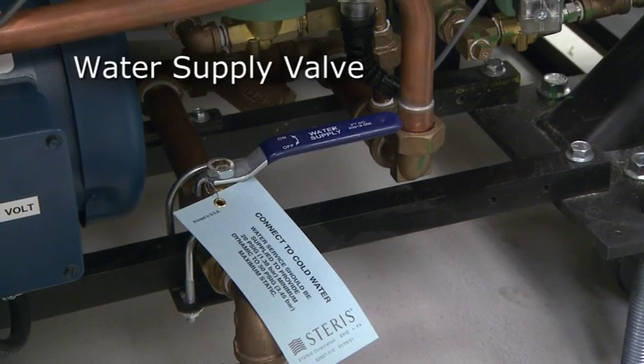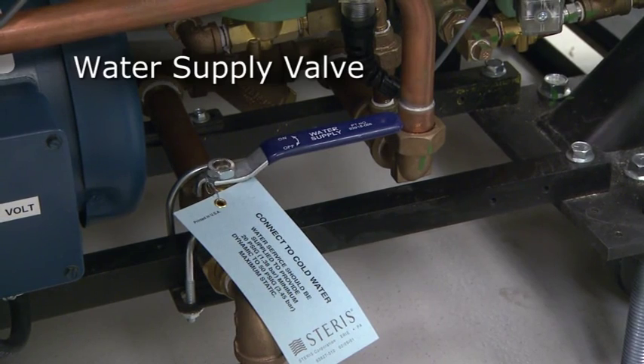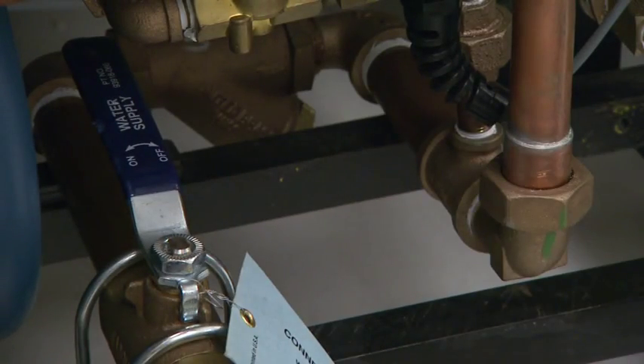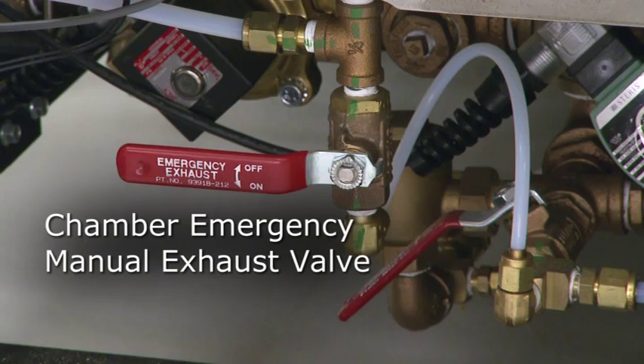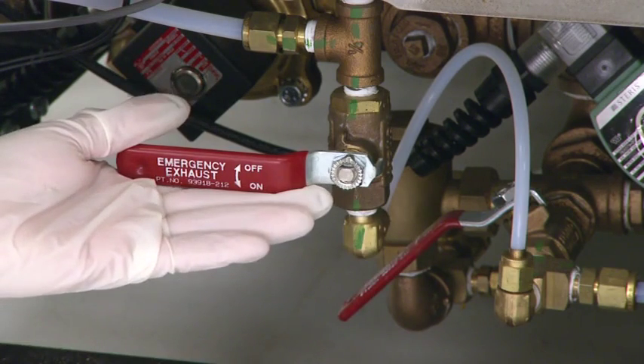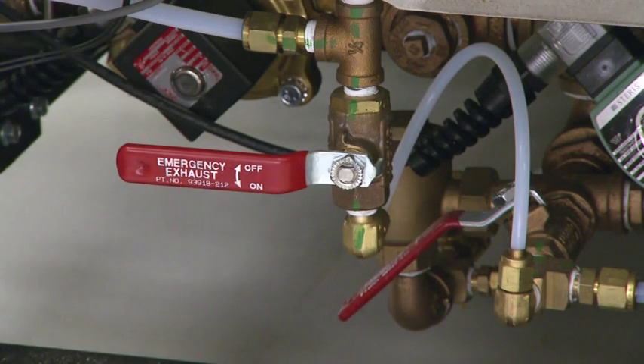The water supply valve is located behind the side access panel or within the wall enclosure below the chamber. Ensure this is in the open position before trying to operate the sterilizer. The chamber emergency manual exhaust valve is used only in emergency situations. The valve is to be left in the closed position for normal operation.